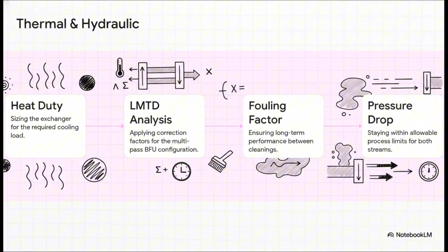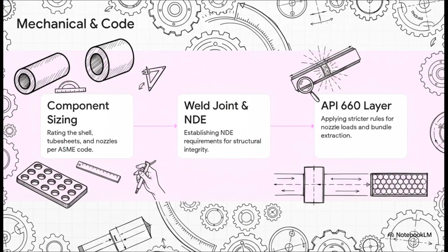Now the mechanical side. Here, ASME code dictates the thickness of every part that holds pressure, and sets the rules for welding and non-destructive examination (NDE) to guarantee structural integrity. API 660 adds another layer of rigor, specifying things like how much clearance you need to pull the tube bundle out for maintenance.